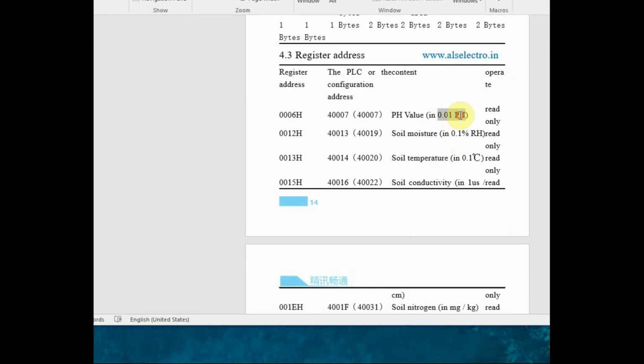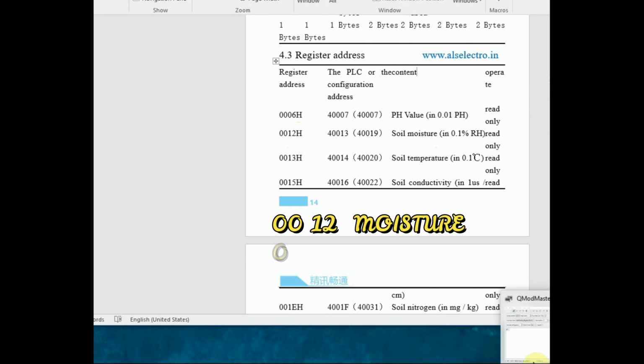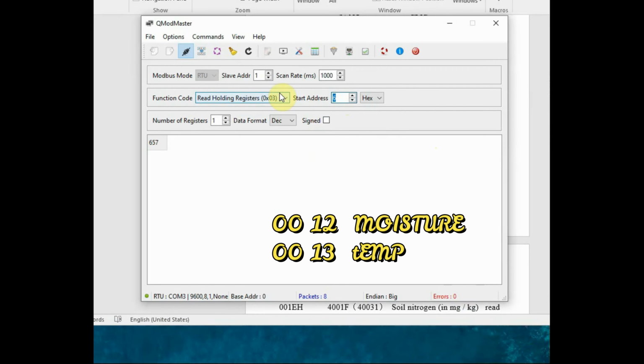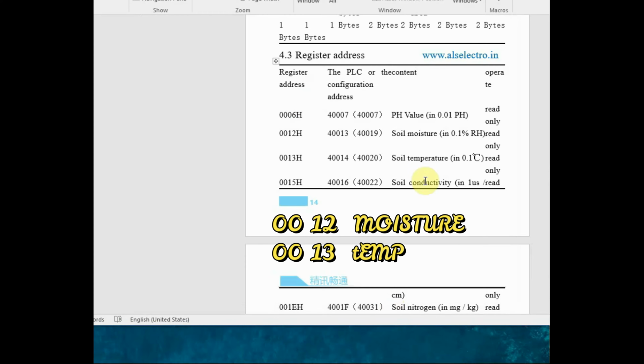The address of the soil moisture, to get the soil moisture value, is 0012 as per the data sheet. Feed in the address as 0012, number of registers 1, click on command read write, you get the soil moisture. This has to be divided by 10 to get the final value.